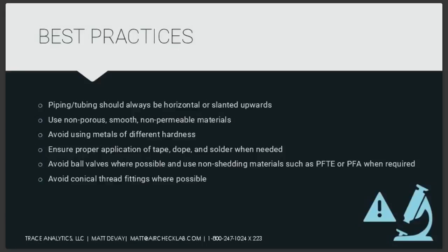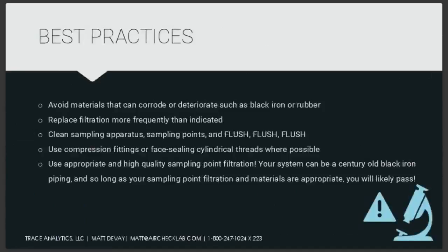Those kinds of things, particularly, I can't count the number of times I see Teflon tape on a microscopy membrane. If you gotta use ball valves, PTFE or PFA material, they tend to be pretty friction-free. They don't shed particles very easily. They require less lubrication, which makes them less likely to become contaminated. Particularly on your point of use or your sampling points, avoid conical thread fittings if you can. Go for face sealing or compression or sanitary type fittings if you can.